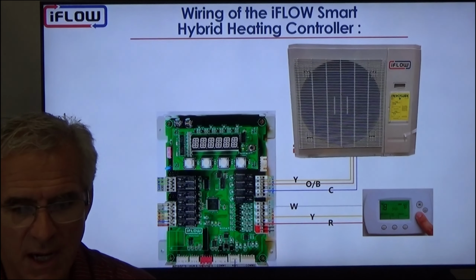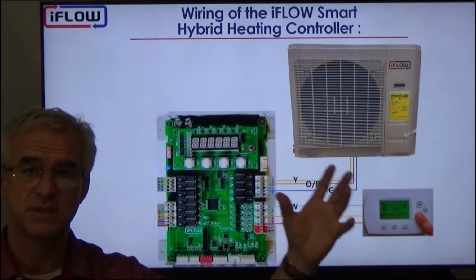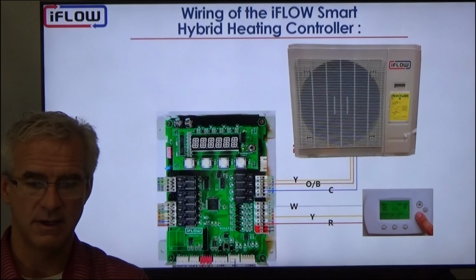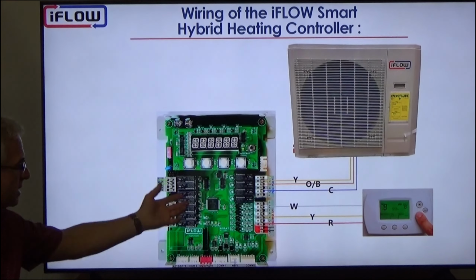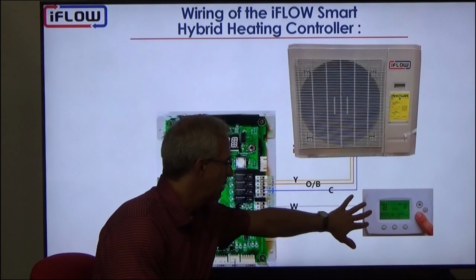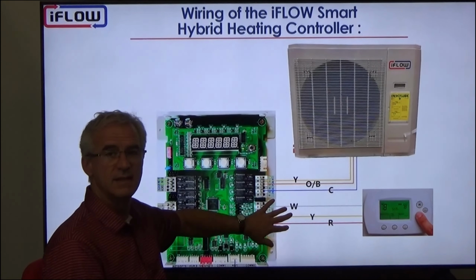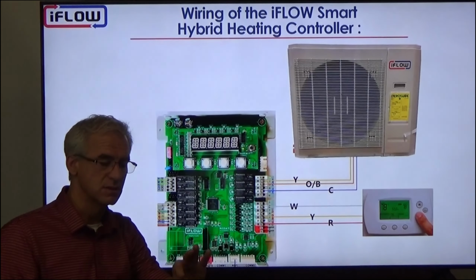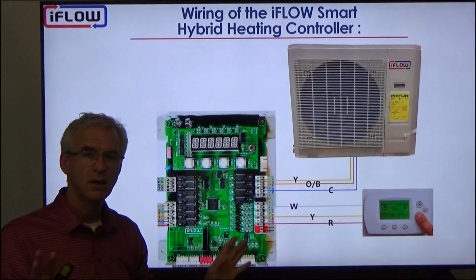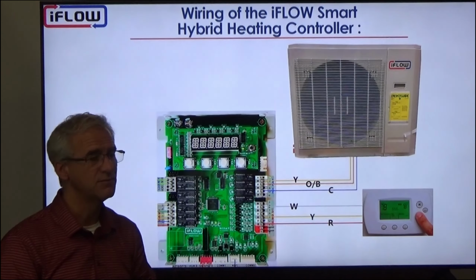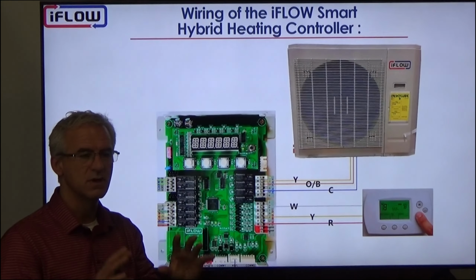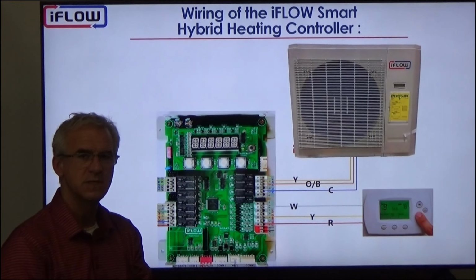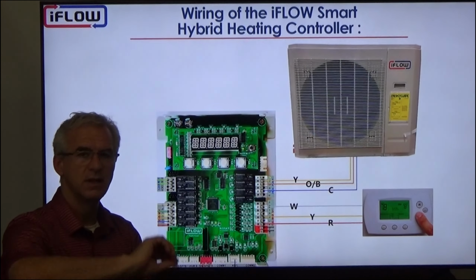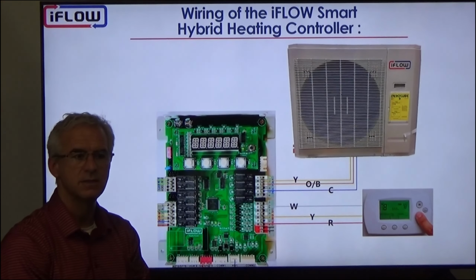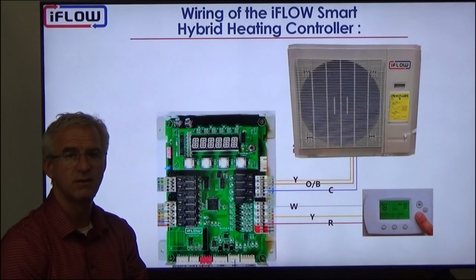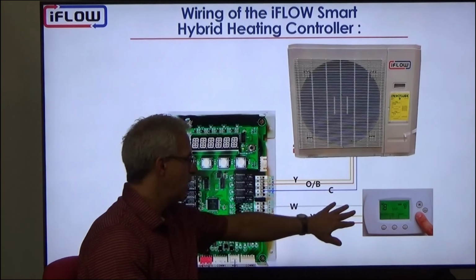If you're using the smart hybrid controller, which is, as I mentioned, if we're using an existing furnace and not the iFLOW air handler, we can use the existing thermostat. So even if you only have a minimum of, let's say, 3 wires, an R, a W, and a Y, not a problem. You don't have to upgrade the thermostat. You don't have to change the wiring in the wall if it's a finished house and you've got a finished basement. Running another line of wire to run a communicating thermostat could be very difficult, very expensive. We can run with that 3-wire.